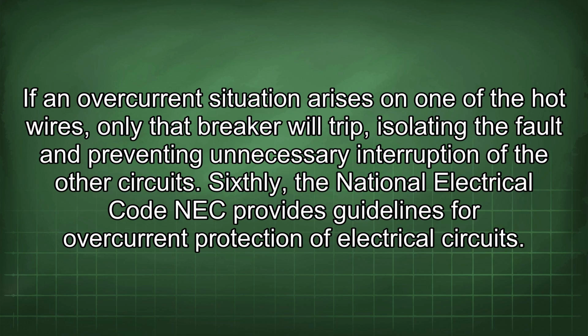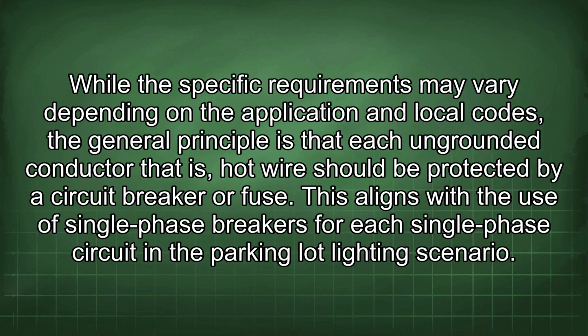Sixthly, the National Electrical Code (NEC) provides guidelines for overcurrent protection of electrical circuits. While the specific requirements may vary depending on the application and local codes, the general principle is that each ungrounded conductor, that is, hot wire, should be protected by a circuit breaker or fuse. This aligns with the use of single-phase breakers for each single-phase circuit in the parking lot lighting scenario.